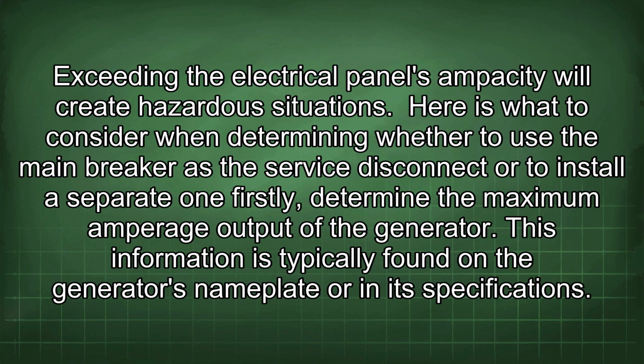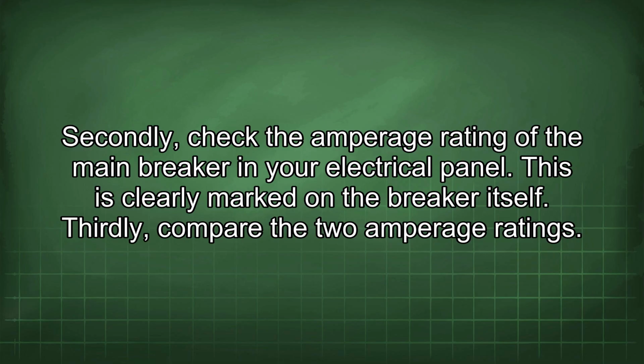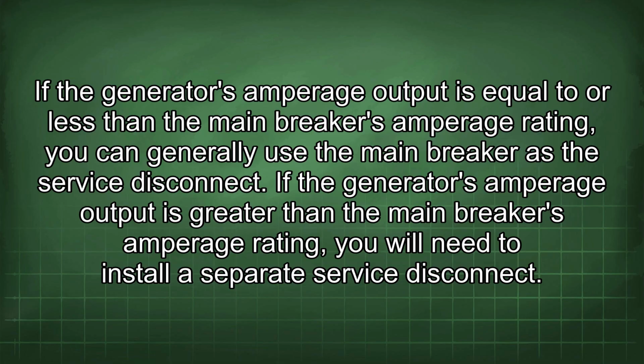Here is what to consider when determining whether to use the main breaker as the service disconnect or to install a separate one. Firstly, determine the maximum amperage output of the generator. This information is typically found on the generator's nameplate or in its specifications. Secondly, check the amperage rating of the main breaker in your electrical panel. This is clearly marked on the breaker itself. Thirdly, compare the two amperage ratings. If the generator's amperage output is equal to or less than the main breaker's amperage rating, you can generally use the main breaker as the service disconnect. If the generator's amperage output is greater than the main breaker's amperage rating, you will need to install a separate service disconnect.